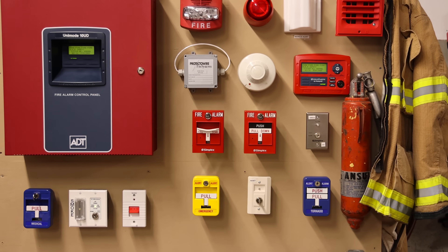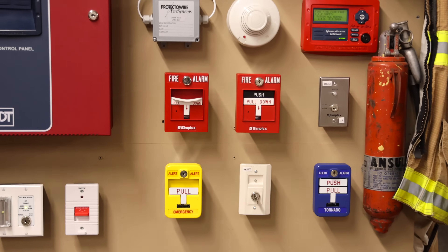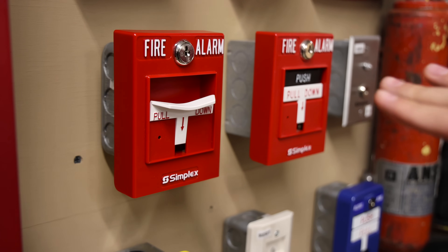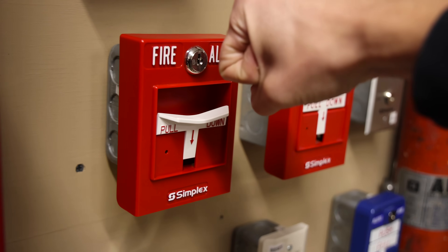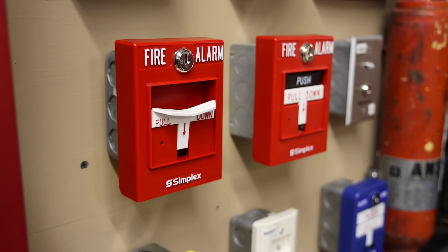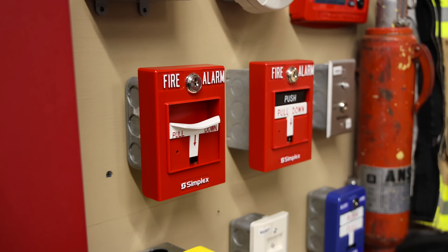For pull stations today, we have two modern ones. On the left is a Simplex 4099-9021 addressable ADA-friendly pull station. What I mean by that is they designed the T-handle on this model to easily be able to be activated even if you don't have fingers. I have a fist here and I can still easily reach in and pull the lever down. It's very important for every person, regardless of their physical situation, to still be able to activate the fire alarm system if they suspect an emergency.